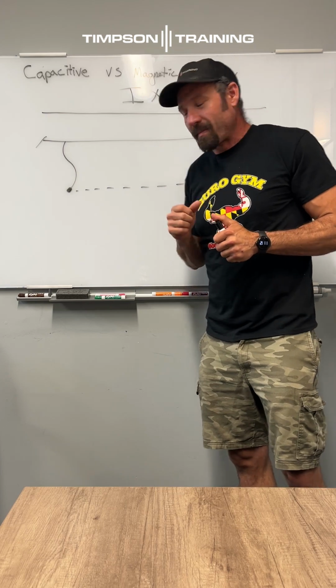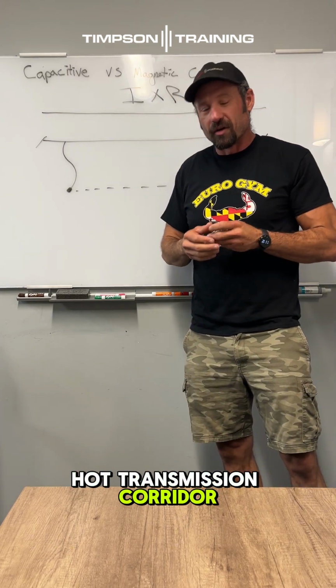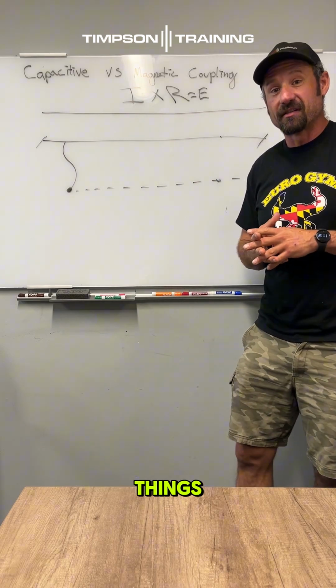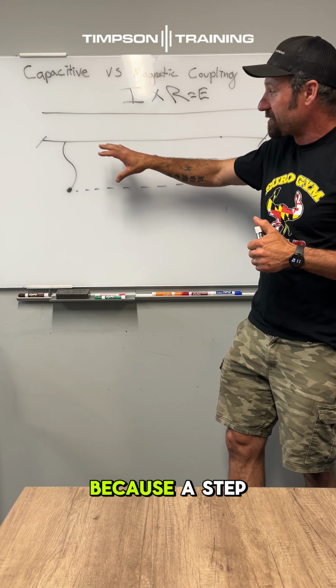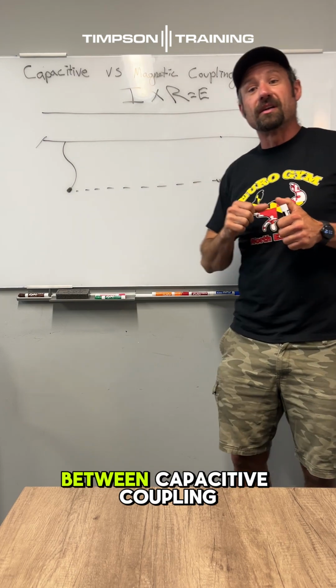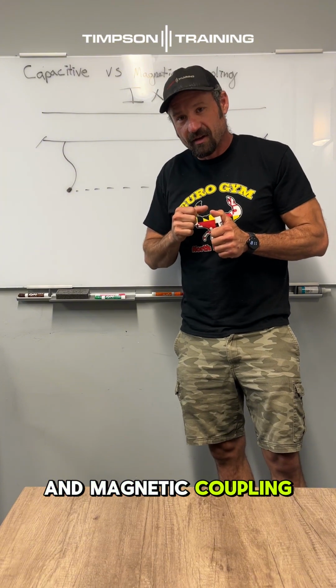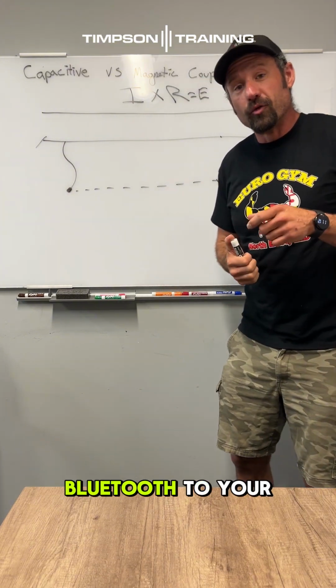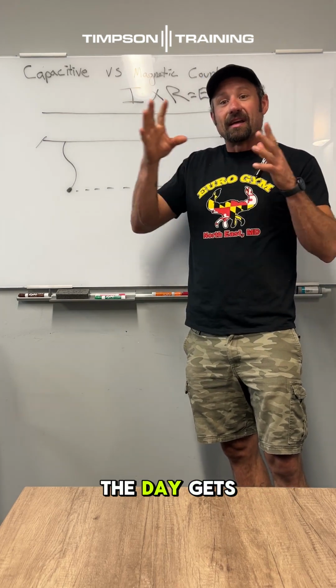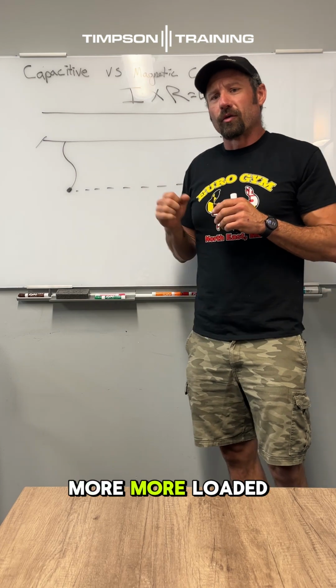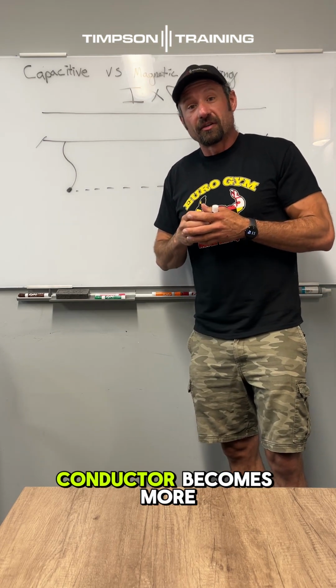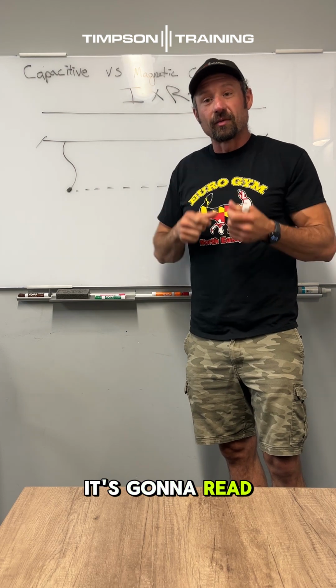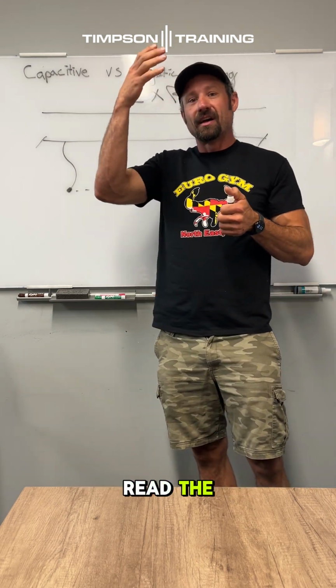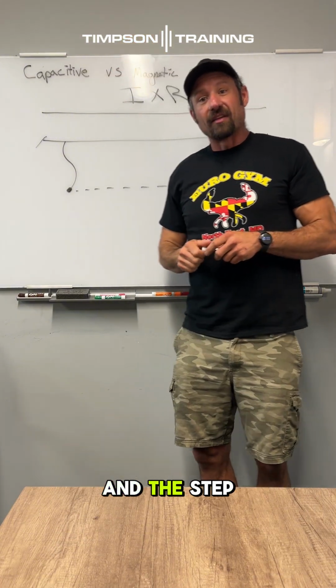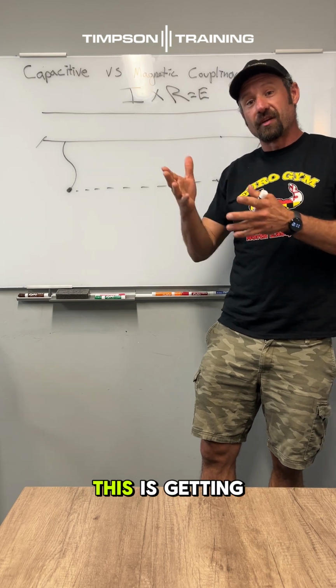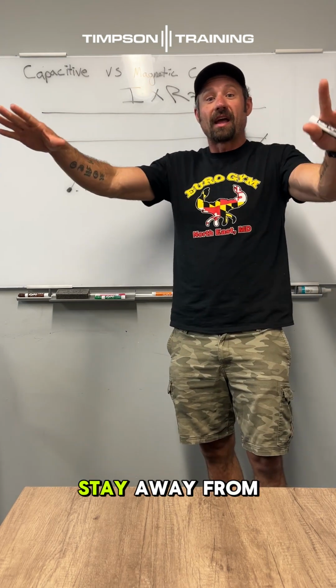Now, here's the tip. If you're going to work in a hot transmission corridor, it's really important that we have certain things like step and touch meters, because a step and touch meter is going to tell you the difference between capacitive coupling and magnetic coupling. A lot of step and touch meters now are Bluetooth to your phone. So as the day gets hotter and that line gets more loaded, and that grounded conductor becomes more dangerous, it's going to read that. That step and touch meter can read the ground current injection and the step and touch potential, and it's going to tell you that this is getting really dangerous and you should stay away from this area.